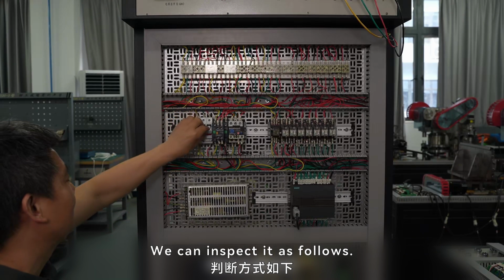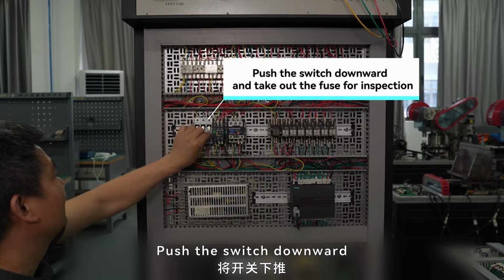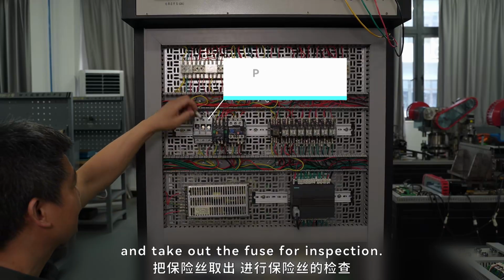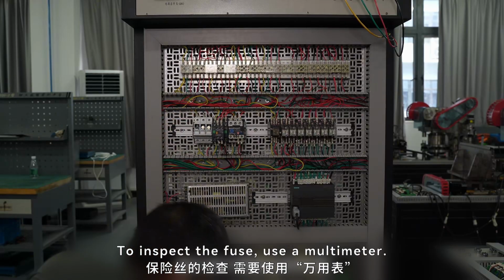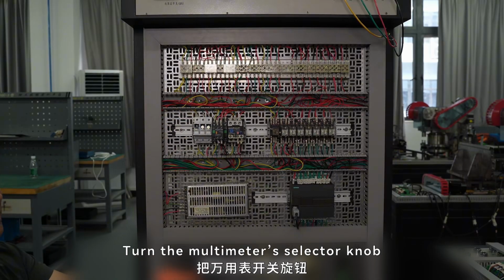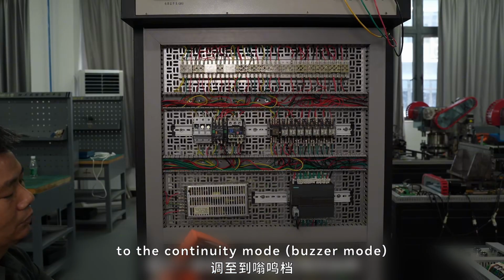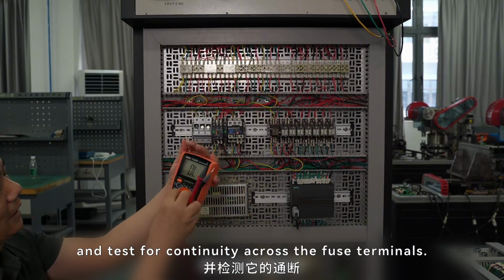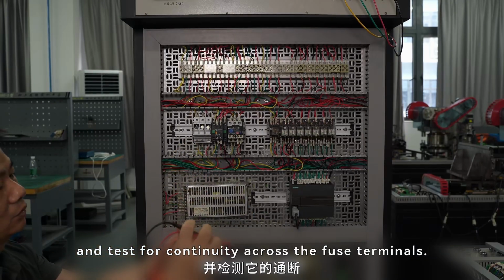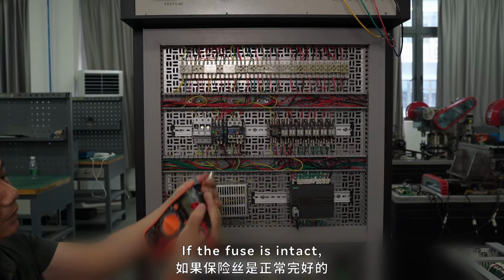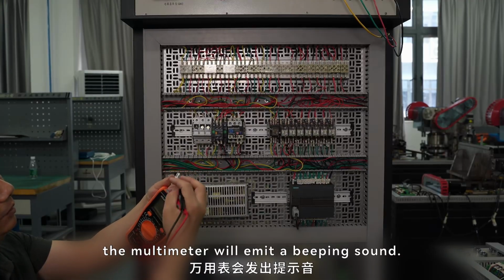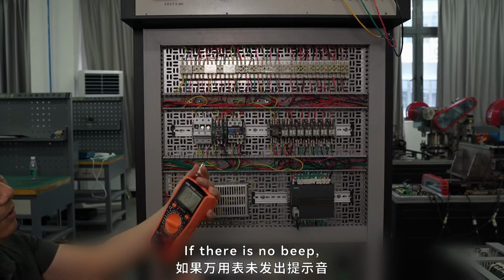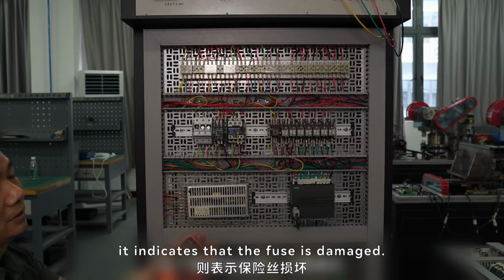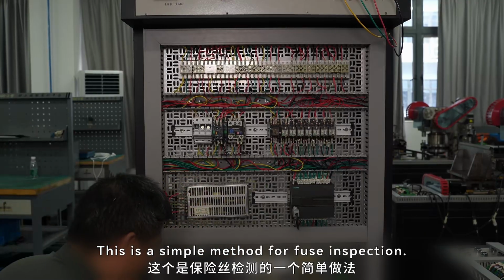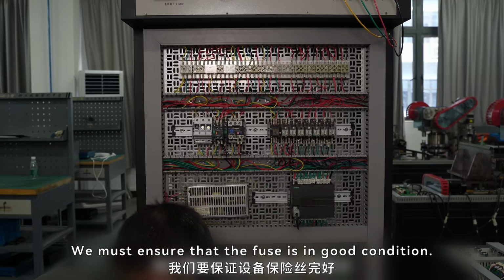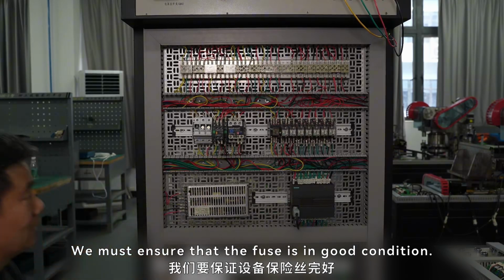We can inspect it as follows. Push the switch downward and take out the fuse for inspection. To inspect the fuse, use a multimeter. Turn the multimeter selector knob to the continuity mode, buzzer mode, and test for continuity across the fuse terminals. If the fuse is intact, the multimeter will emit a beeping sound. If there is no beep, it indicates that the fuse is damaged. This is a simple method for fuse inspection. We must ensure that the fuse is in good condition.